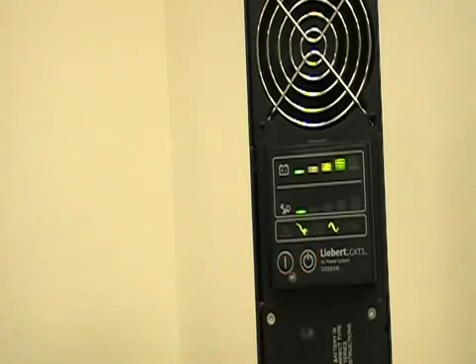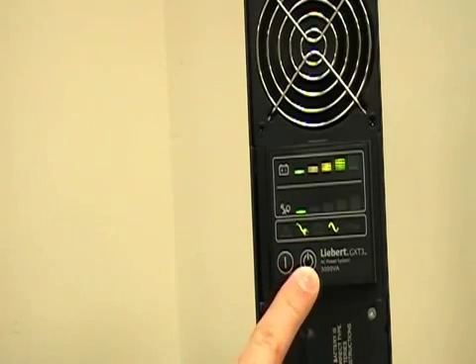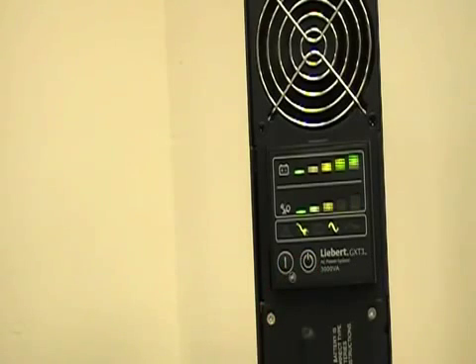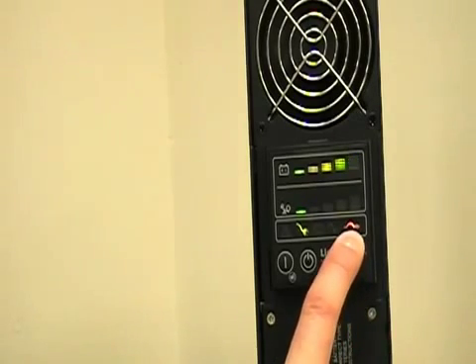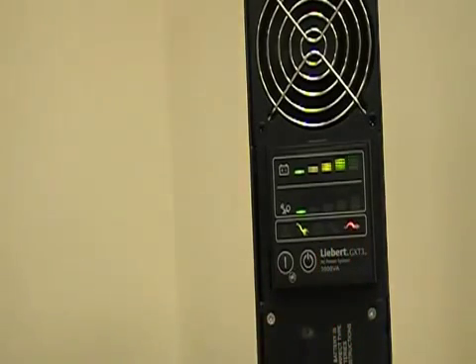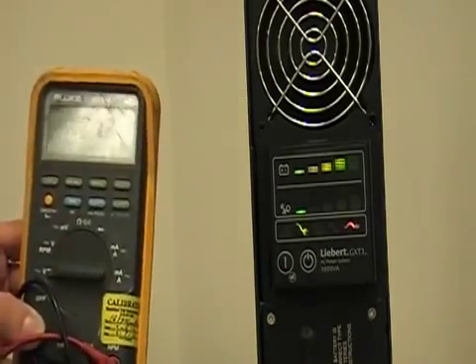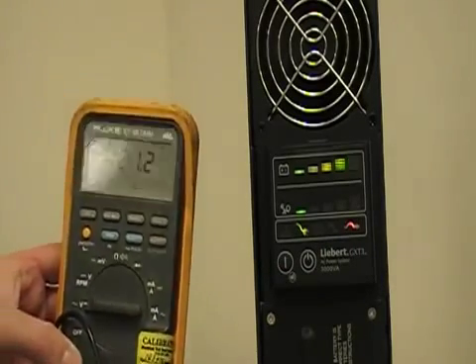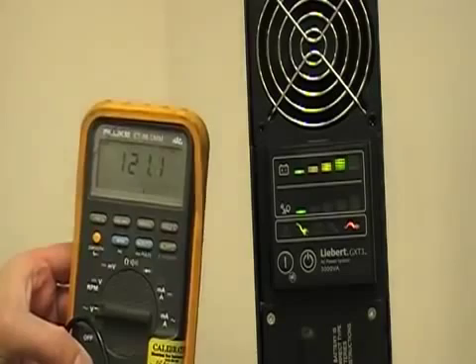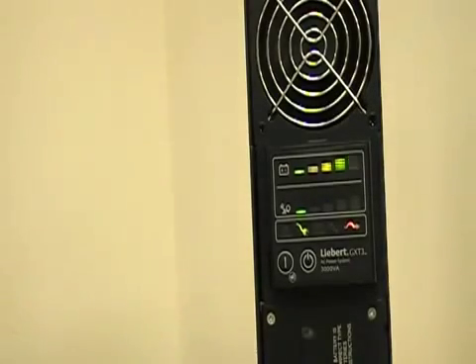The ideal way to do it would be to transfer the unit to bypass. Press and hold the circle with the line. It'll indicate with one long beep, and you'll see the orange bypass light come on. At that point we still have output, but you'll notice the voltage change. I was at 119 on line, now I'm at 121.1, essentially on bypass through the machine.